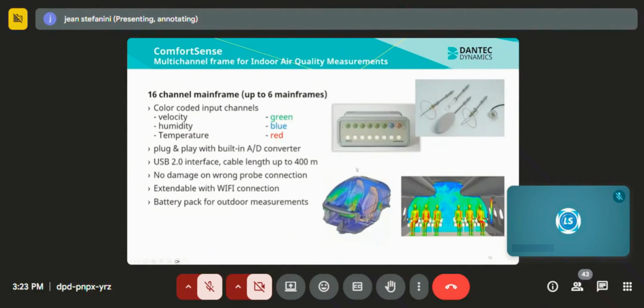In opposition, let's go quickly through this one. We also have the same kind of device, but with much bigger sensors mainly used for industrial applications. This is what we call a ComfortSense, where you can measure temperature, velocity, and humidity. It's mainly for indoor air quality, or if you want to do a quick check of your flow, because the probes are very big and robust, but your spatial and temporal resolution is very poor compared to a standard CTA module.